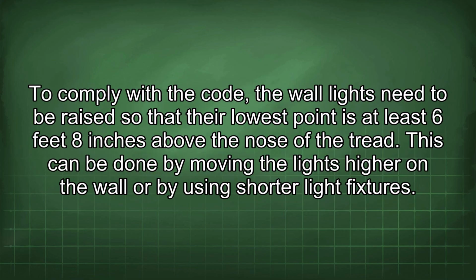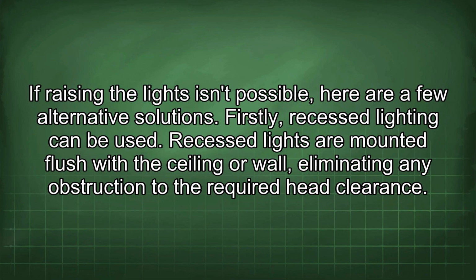To comply with the code, the wall lights need to be raised so that their lowest point is at least 6 feet 8 inches above the nose of the tread. This can be done by moving the lights higher on the wall or by using shorter light fixtures. If raising the lights isn't possible, here are a few alternative solutions. Firstly, recessed lighting can be used. Recessed lights are mounted flush with the ceiling or wall, eliminating any obstruction to the required head clearance.